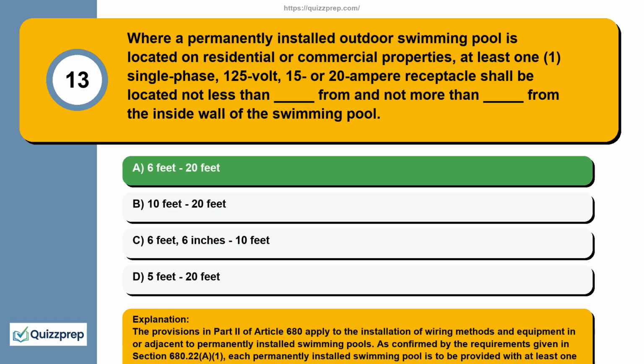This requirement allows ordinary appliances such as a radio to be safely plugged in and used near the pool, but avoids the need for extension cords in the pool vicinity. Be advised the receptacles must be provided with GFCI protection. 680.22 a. 4.